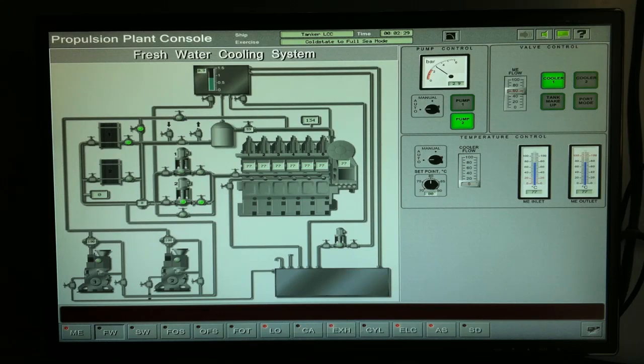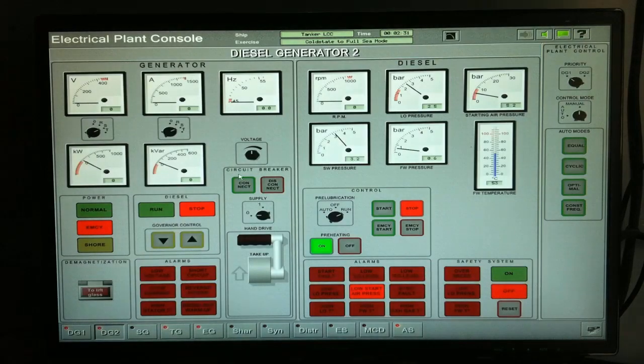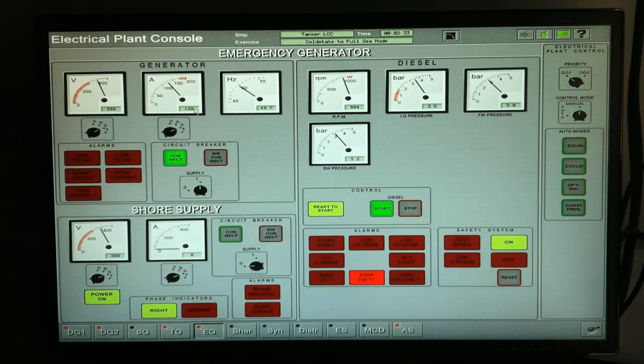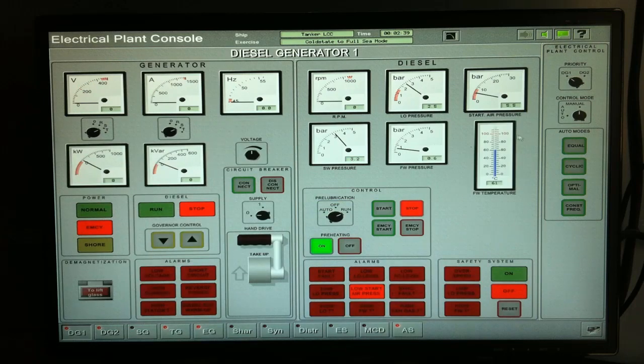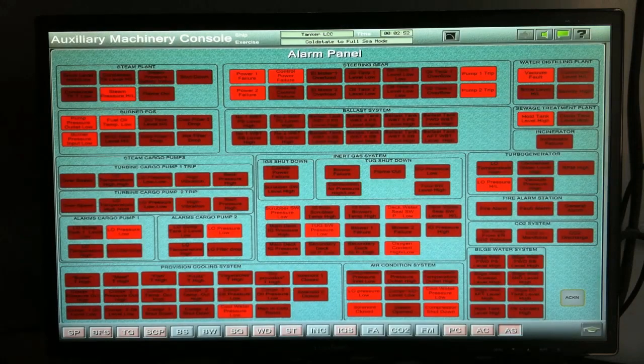Okay, then we check the emergency generator load. Okay, so we have 128 amperes. Check on the generator. Starting air pressure, it's not enough. You need 8.5 starting air pressure in order to start the generator. So for the meantime, we prepare the boiler first.